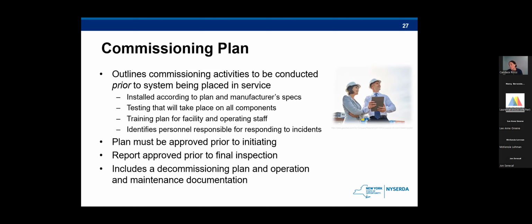You need to provide the conditions under which all testing will be performed, documentation of the owner's project requirements and basis of design necessary to understand the installation and operation of the system, and verification that the required equipment and systems are installed in accordance with the approved plan. You need to provide the integrated testing for all fire and safety systems, and the testing for any required thermal management, ventilation, or exhaust systems associated with the energy storage installation. You also need to provide the preparation and delivery of the operation and maintenance documentation, which we'll discuss on the next slide.